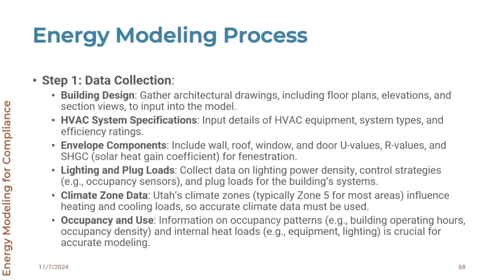Some of the things you're going to want to know: how the building operates. We talked about schedules before - usually you focus on occupancy schedules, and most other schedules follow the occupancy of the building. You'll start turning fans on an hour before people show up, and turn them off an hour or so after people leave, for a typical office building. Your lighting schedule follows occupancy, your plug load schedule follows occupancy, temperature schedules follow occupancy, and outside air flows and minimums follow occupancy for the most part. So when dealing with an energy modeler, you generally want to start with the occupancy schedule and talk about that, since most other things fall into place based on it.